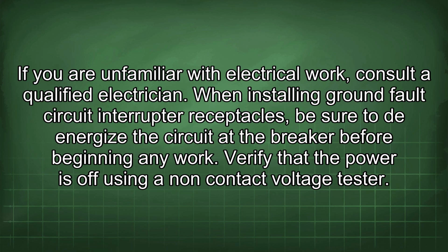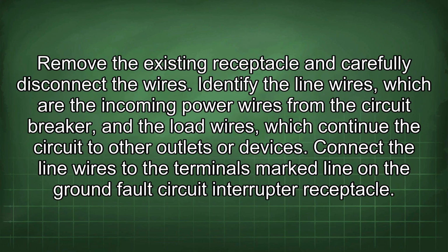When installing ground fault circuit interrupter receptacles, be sure to de-energize the circuit at the breaker before beginning any work. Verify that the power is off using a non-contact voltage tester. Remove the existing receptacle and carefully disconnect the wires. Identify the line wires, which are the incoming power wires from the circuit breaker, and the load wires, which continue the circuit to other outlets or devices.